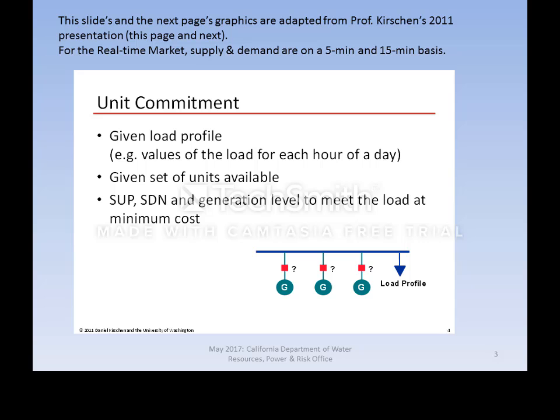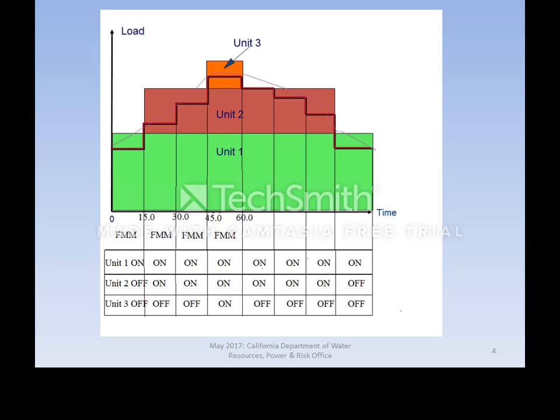Physical characteristics include capacity in megawatts, start-up time, transition time, shutdown time, maximum ramp rate, and minimum operation level. The load profile over a period of time is divided into 15-minute intervals. With three units available to follow load: Unit 1 is shown operating at full production for all 15-minute intervals in the example. It is assumed that Unit 1 started in a prior interval because all units have a finite startup time.